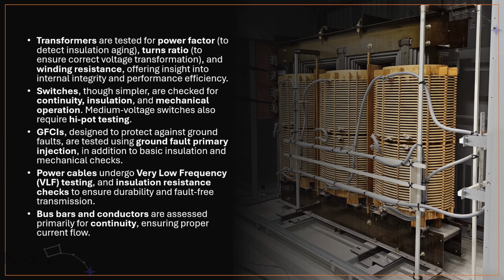According to the NFPA 70B, it is not enough to simply perform these tests. They must also be recorded, reviewed over time, and used to guide future maintenance decisions. Equipment without a well-documented test history represents a blind spot for both compliance and operational risk.